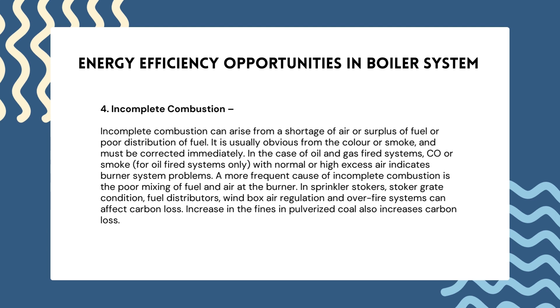With coal firing, unburnt carbon can comprise a significant loss, occurring as grate carry-over or carbon in ash, amounting to more than 2 percent of heat supplied. Non-uniform fuel size is a major reason for incomplete combustion. In chain grate stokers, large lumps will not burn out completely while small pieces and fines may block air passages, causing poor air distribution. In spreader stokers, fuel distributors, wind box, air regulation and over-fire systems can affect carbon loss. Increased fines in pulverized coal also increases carbon losses.